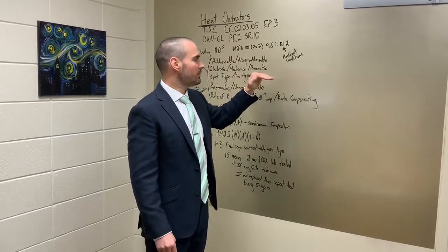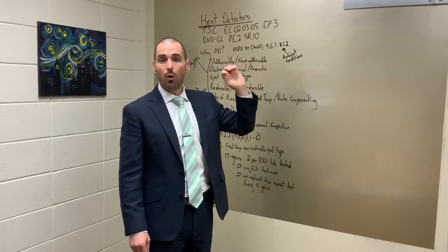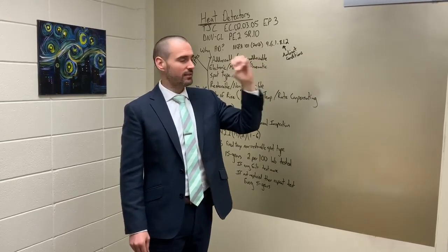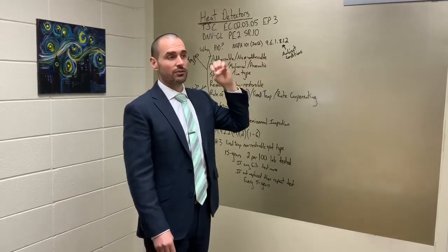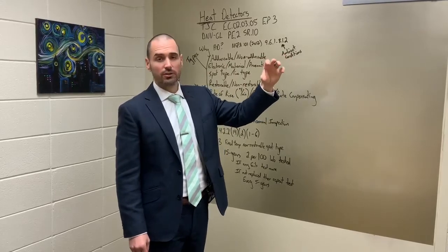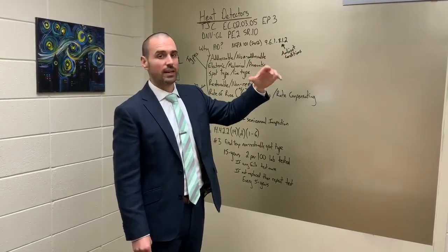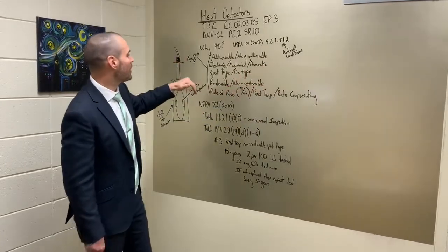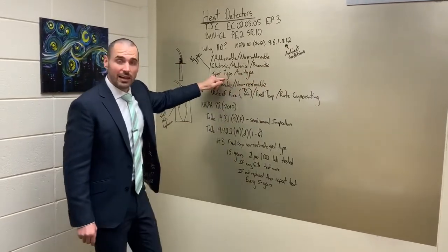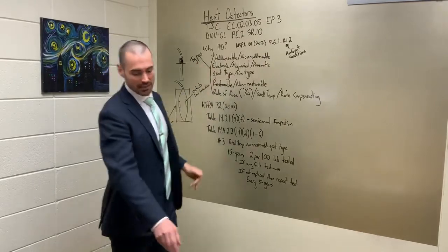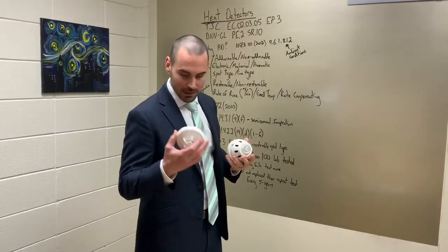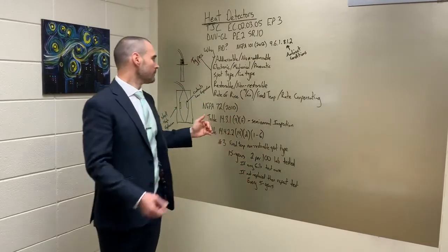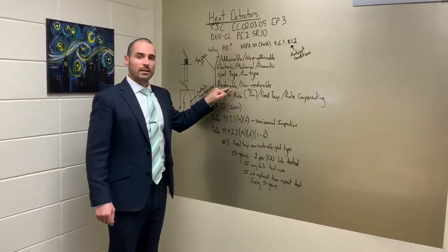We'll talk real quickly line type. There's two different kinds. There's cords that actually can sense the temperature, and then there's pneumatic tubes where the pressure differential inside those pneumatic tubes changes and it triggers an alarm. Primarily used in industrial settings. So what we see most of the time in healthcare is spot type detectors. All of these are different spot type detectors that you'll find.